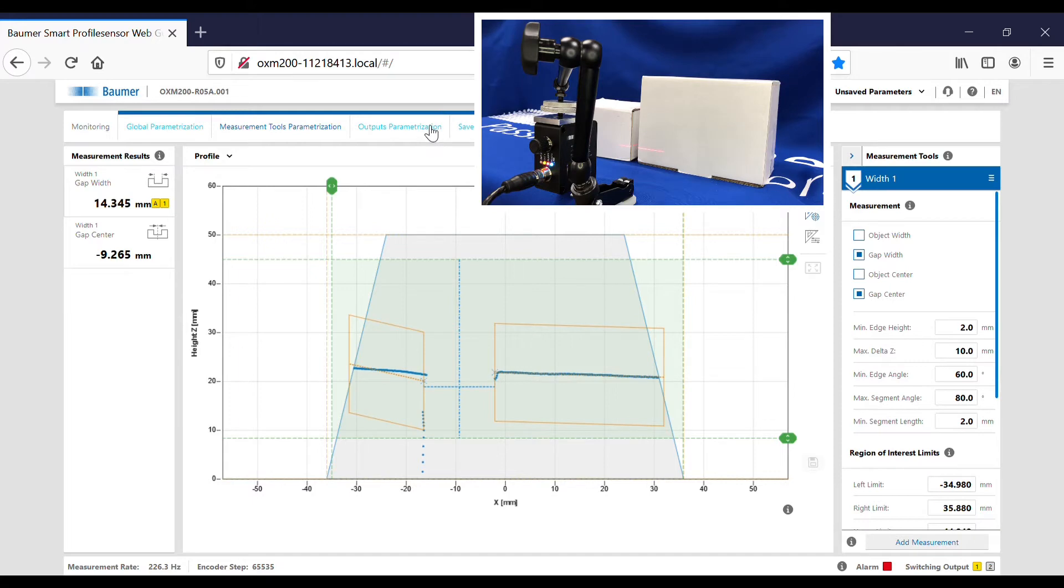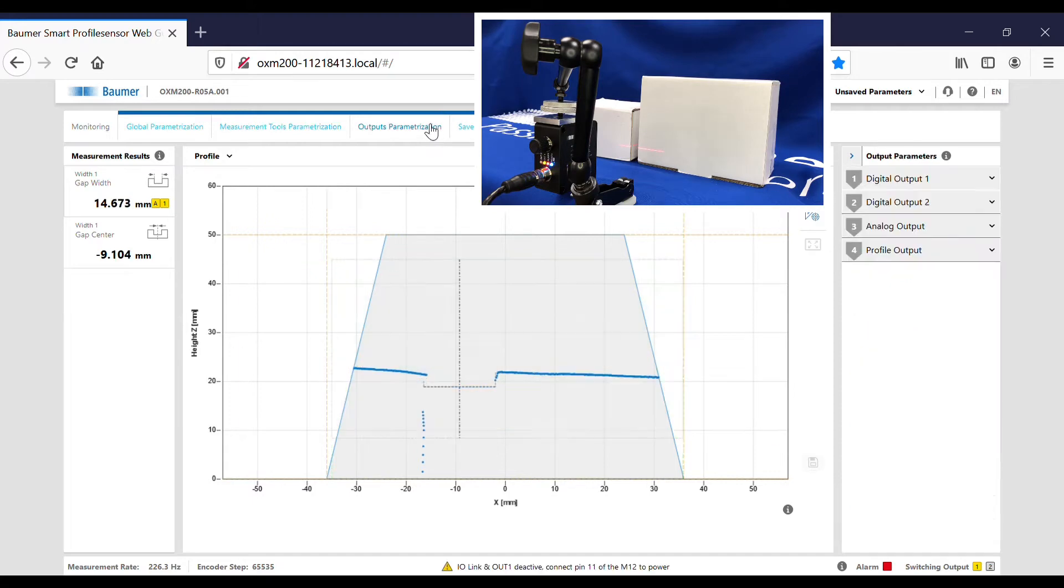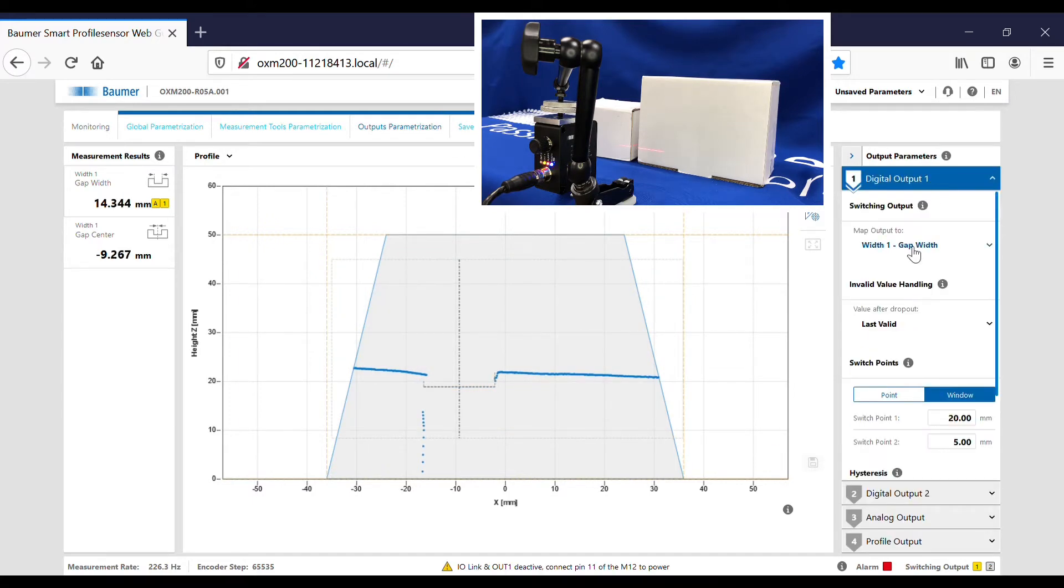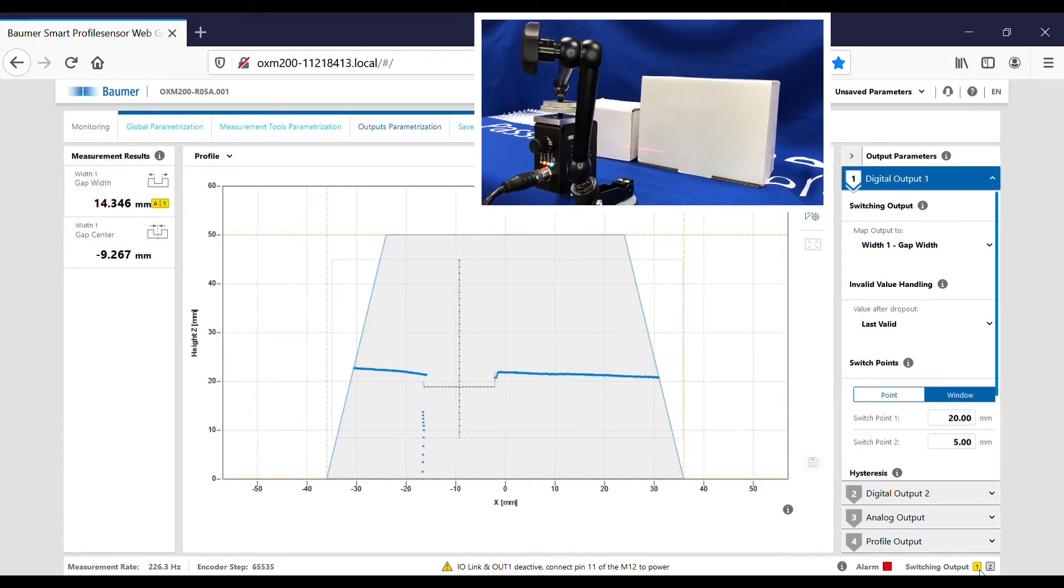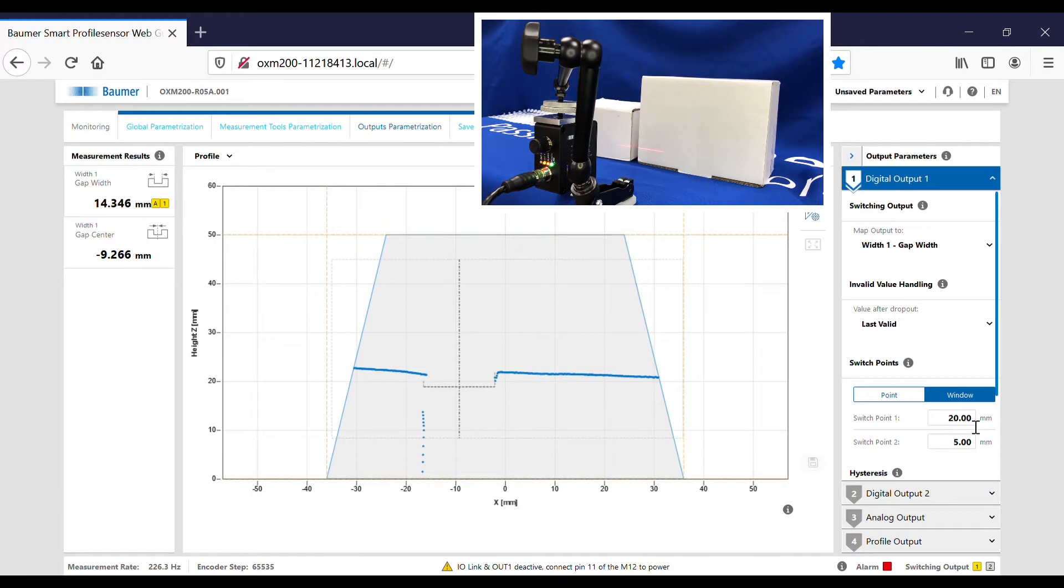If I show you where the outputs are, I've assigned the digital output to the gap width and you can see the output turning on and off here. I've set the switch point between 5 and 20 mil is okay, outside of that is no good.